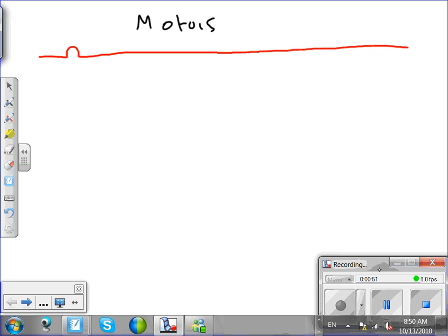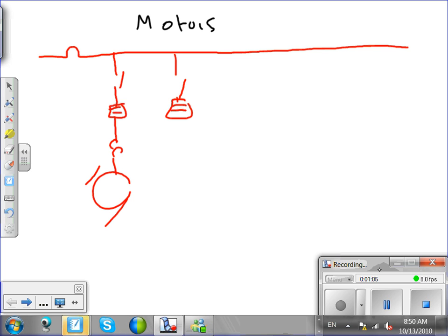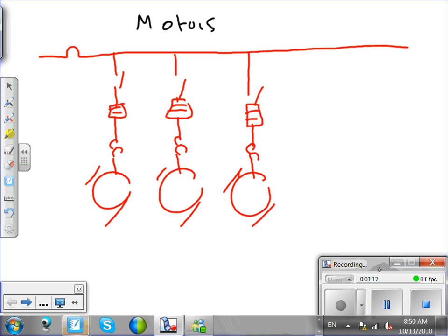My overcurrent protection device, I have a couple of motors with an overcurrent protection device and an overload and a motor. A couple of them. Anybody has a problem with that? Overcurrent protection device. Another motor, overcurrent protection device, overload, and a motor. And a third one, overcurrent protection device, overload, and a motor. Okay, I have 3 motors connected to the same feeder, tapped from the same feeder.